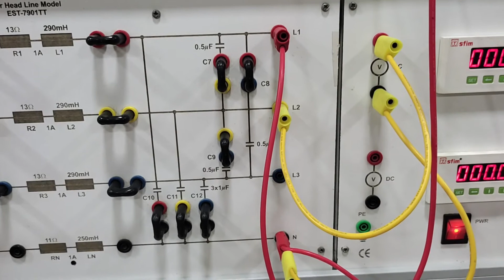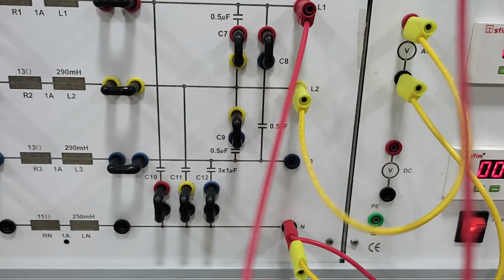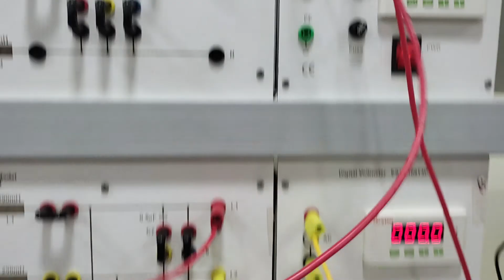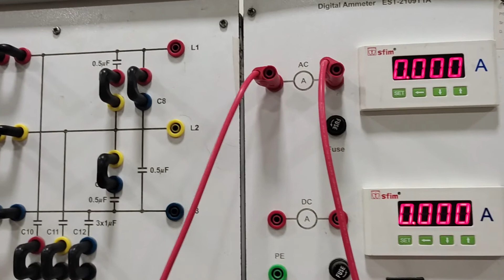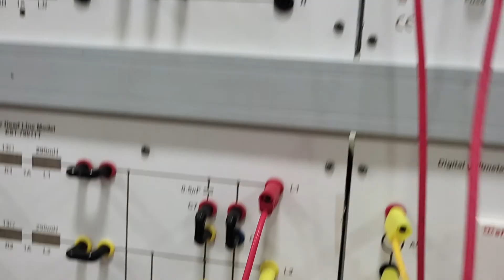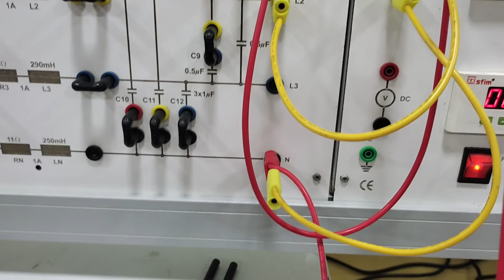So students, from the figure we have already discussed that we can directly connect this L1 phase towards our neutral, but as in the procedure we have to measure this short circuit current. Therefore we have first connected the L1 phase with the ammeter, and then from the ammeter it is connected, ammeter is connected in series. So from the ammeter it goes towards our earth, that is the neutral point. So here we have short circuited our first phase with the neutral by connecting an ammeter in series in order to measure the short circuit current.